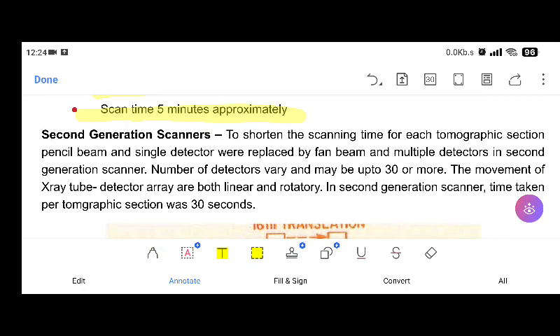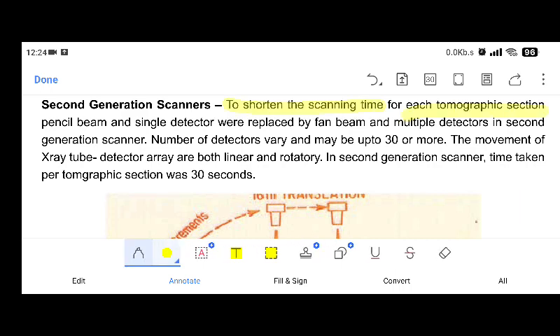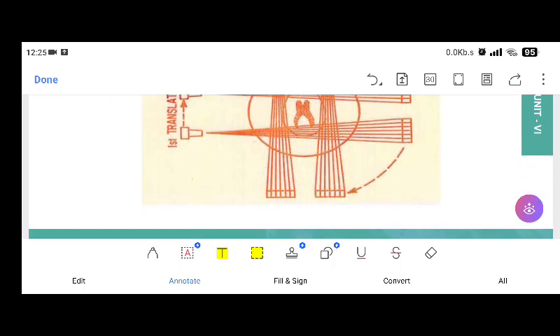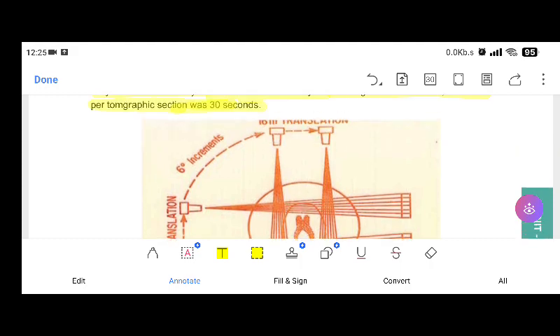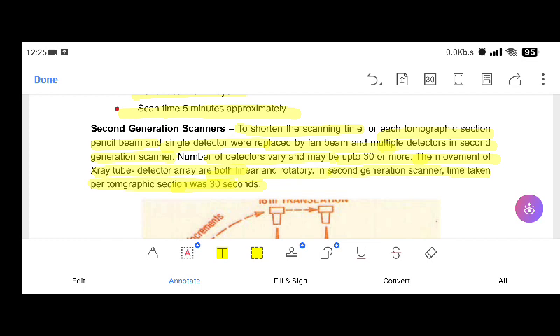Second generation scanners. To shorten the scanning time for each tomographic section, the pencil beam and single detector were replaced by a fan beam and multiple detectors. In the second generation scanner, the number of detectors varies, maybe up to 30 or more. The movement of the X-ray tube and detector array is both linear and rotatory. In the second generation scanner, the time taken per tomographic section was 30 seconds. This was the second generation, with a small fan beam and multiple detectors, maybe up to 30 or more.